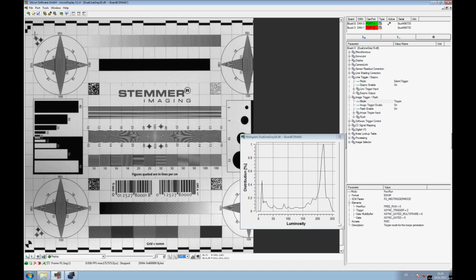So if we look at this region, we have a maximum value around 210. In the middle, it's also in that region, and on the right part, it's the same. So we have a much more uniform image when we are using the flat field correction.